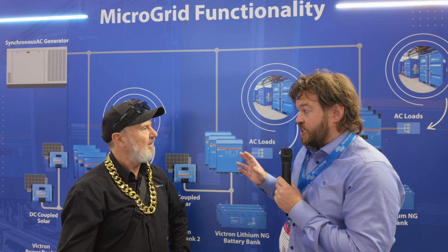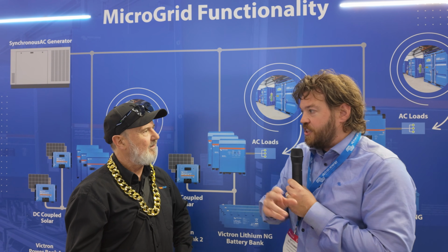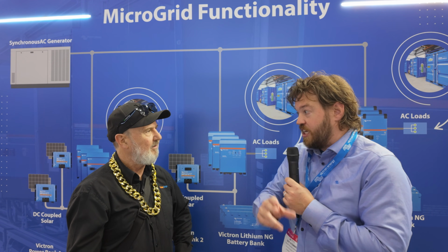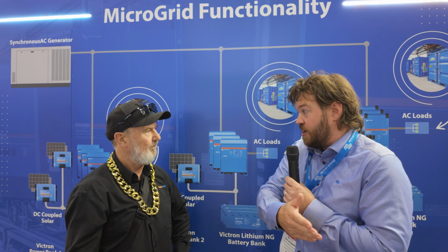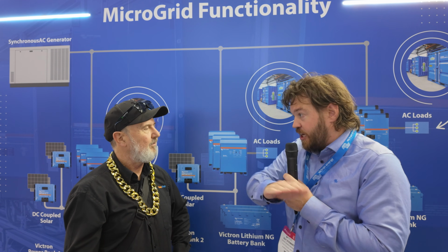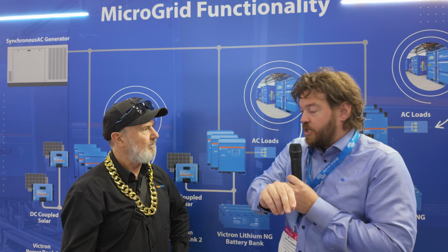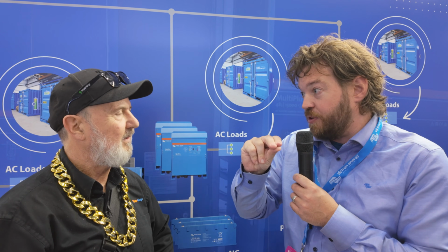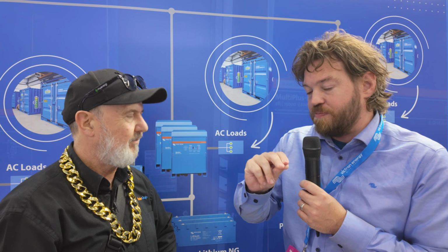And what it does is, in a normal Victron system out of the box, the AC input is never live. So it looks on the AC input and says, is there a supply there? If it is, can I connect to it? It'll try and synchronize with it. If it can, it'll close the relay, it'll start charging the battery or start running the loads or whatever. What this firmware revision does, and what this technology does, is it looks on the AC input and says, is there a supply there? If there is, I'll do what I do. I synchronize and then connect to it. And at that point of connection, there's no load on the AC input relay. So it's very safe, very low duty for that component.